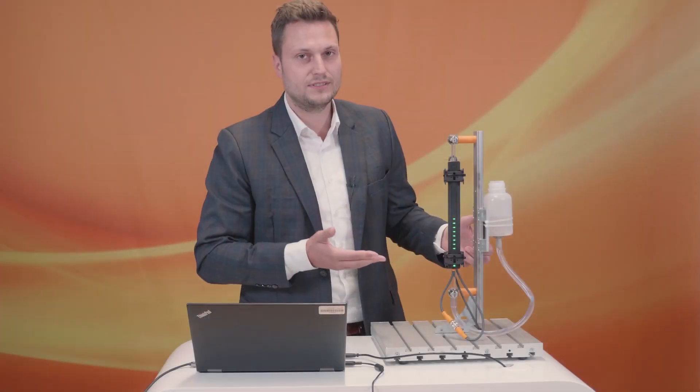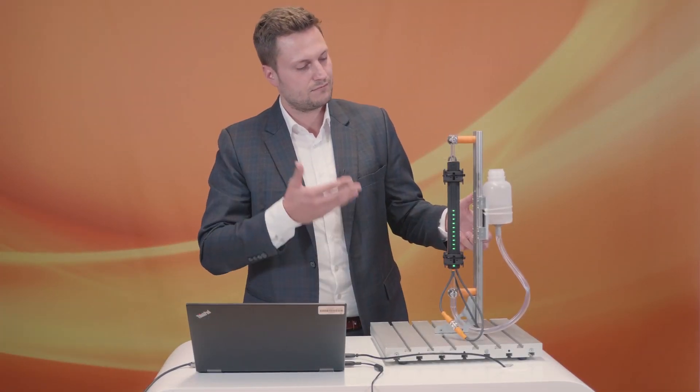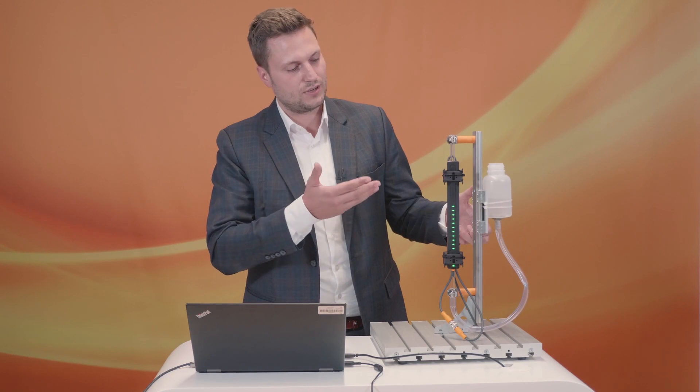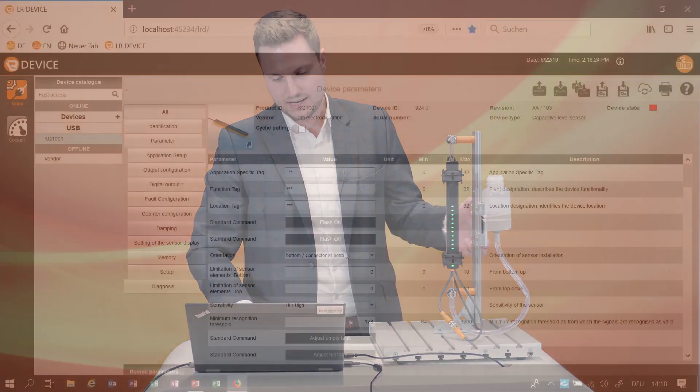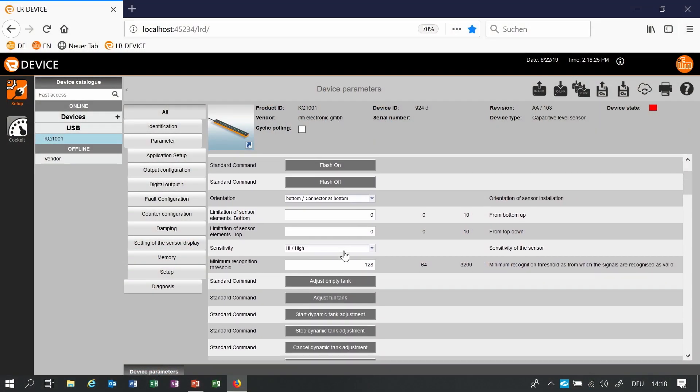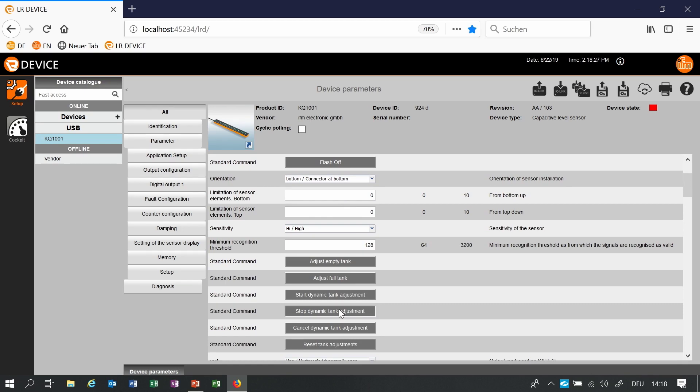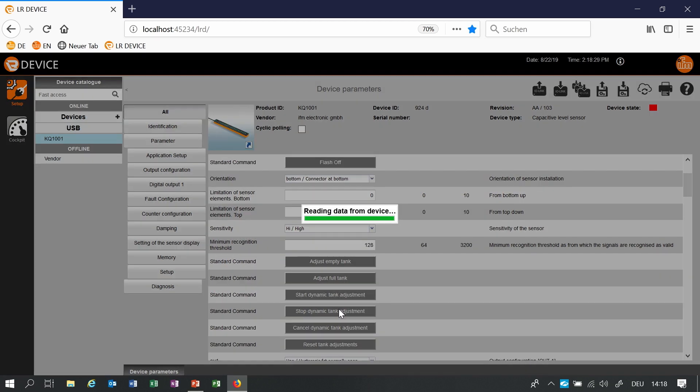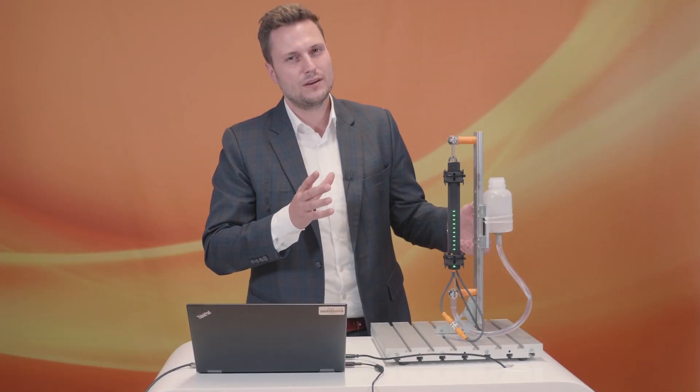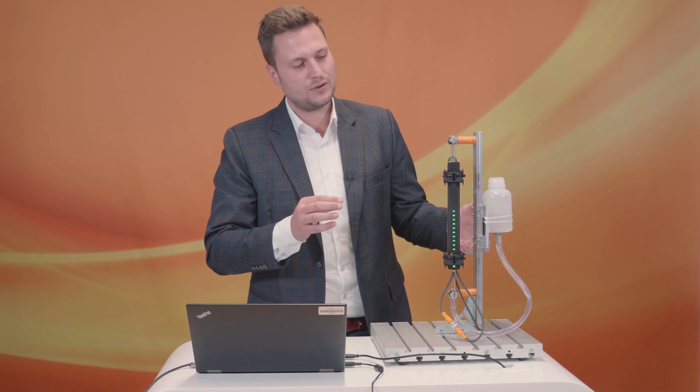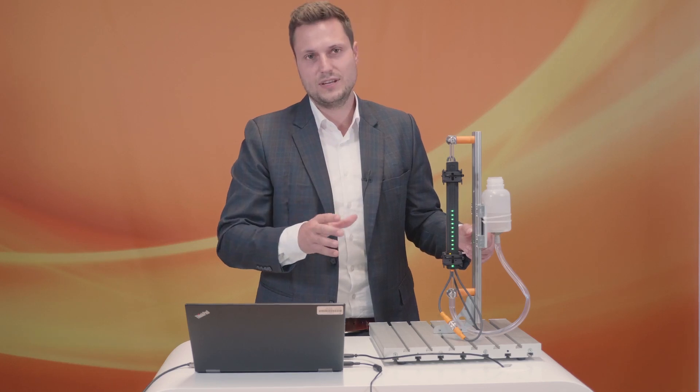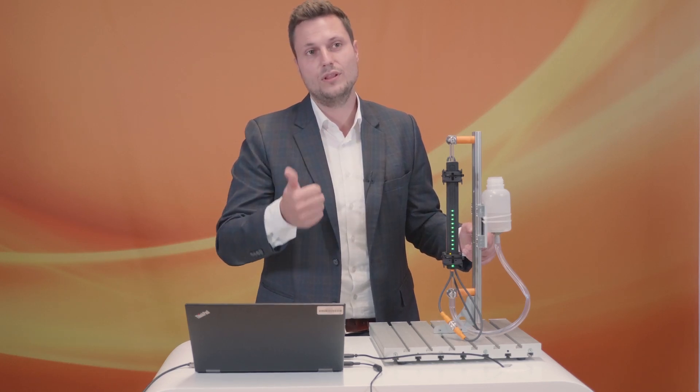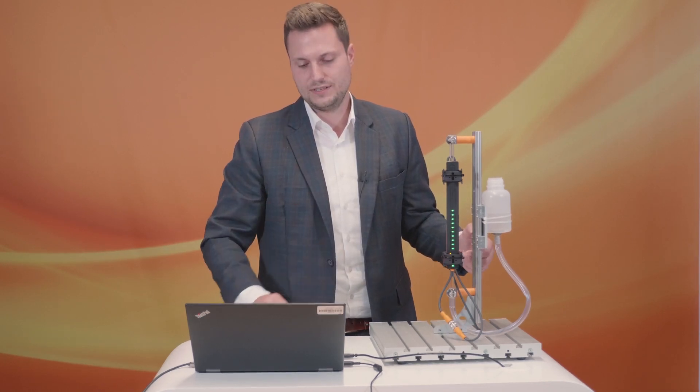As you can see the sensor is already working. Now your machine can work, you can measure the level and after a while you stop the dynamic teach and the sensor is set. In this case beware a little bit because the precision of this tank adjustment is not as good as it would be with a full and an empty teach.